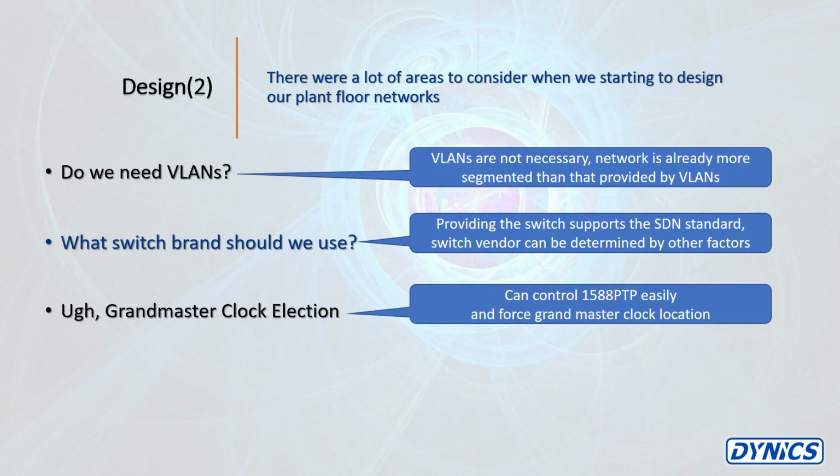In the world of SDN, I have absolute control over my Grandmaster clocks. I can determine who, what, and where the clocks are. I could have one clock. I could have a clock in every single station. I can let only that PLC talk to these servos with 1588 PTP. Therefore, I know who the election will be.